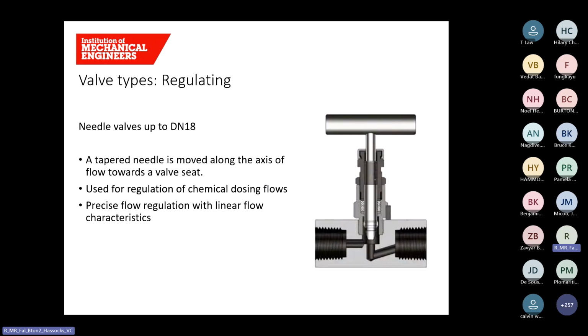Needle valves are used for the regulation of flow in small diameter pipework, typically up to DN18. They consist of a tapered needle which moves up and down in the axis of flow towards a valve seat, allowing more or less flow to pass through. They're used for chemical dosing applications usually and give a very precise and linear flow characteristic.